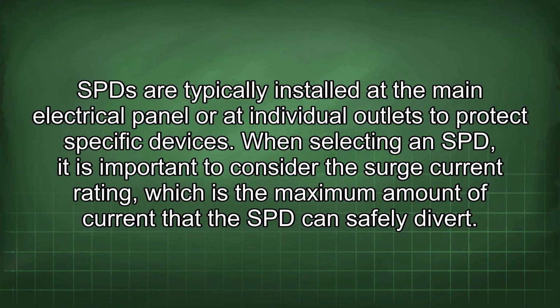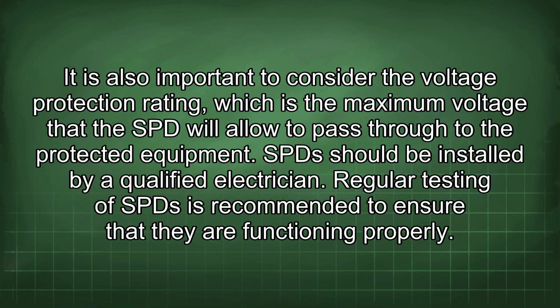When selecting an SPD, it is important to consider the surge current rating, which is the maximum amount of current that the SPD can safely divert. It is also important to consider the voltage protection rating, which is the maximum voltage that the SPD will allow to pass through to the protected equipment. SPDs should be installed by a qualified electrician. Regular testing of SPDs is recommended to ensure that they are functioning properly.